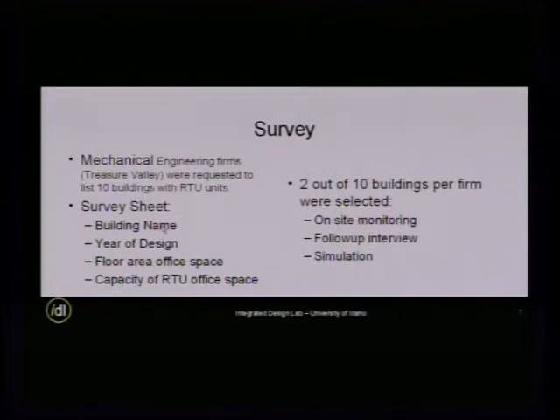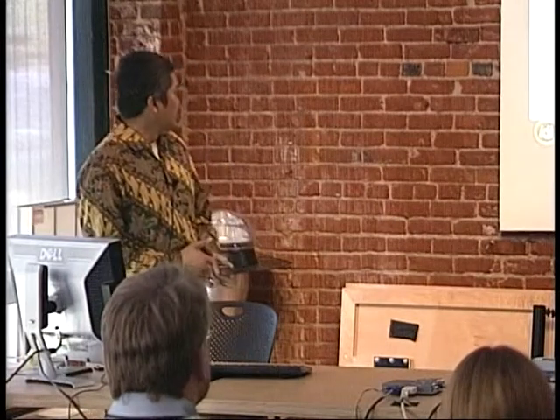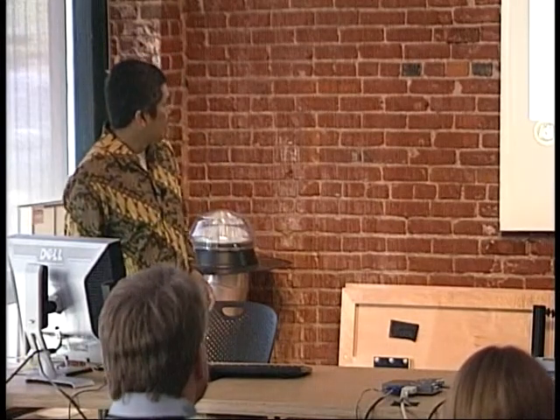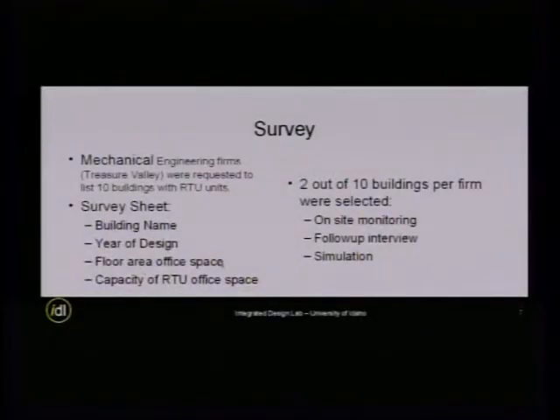So the survey, we sent it out to mechanical engineering firms throughout the Treasure Valley, and we requested from each firm 10 buildings. If possible, 5 each, 5 old and 5 new. So it's very general: building name, year of design, floor area of the office space, and then the capacity of the RTU serving that office space. And then 2 out of the 10 buildings were selected, and then we did on-site monitoring and then follow-up interview and then simulation.